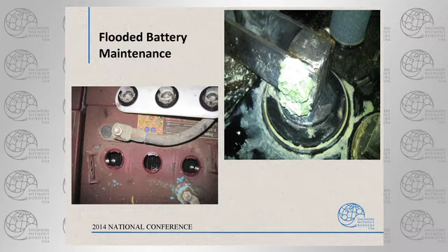So you're going to squeeze the bulb, put it into the electrolyte, draw a sample in, take a reading, put it back in the same cell, squeeze it out, rinse the hydrometer out, and go to your next one. In this case, we've got a vertical, and you read it at the fluid level if you've got a float type one like this.